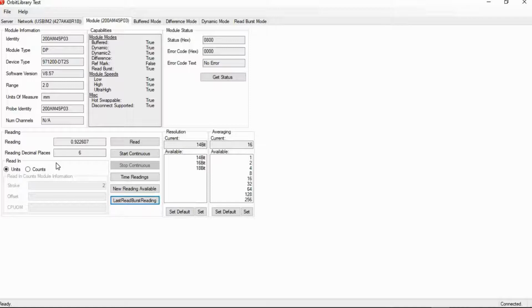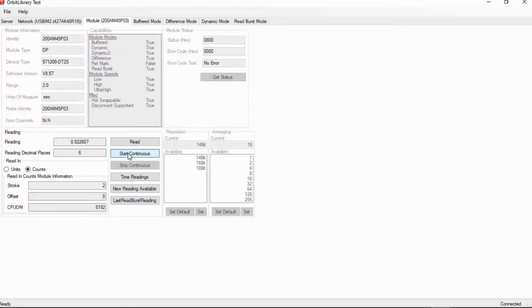Basically, how the digital module works is that it converts the signal from the probe to digital bits and then scaled to the unit of measure. In this case, it's scaled to 2 millimeters. So if you switch to counts, and then let's click Start Continuous, see how now it's reading from about 7,700 bits to about 13,000 bits as I move the probe.